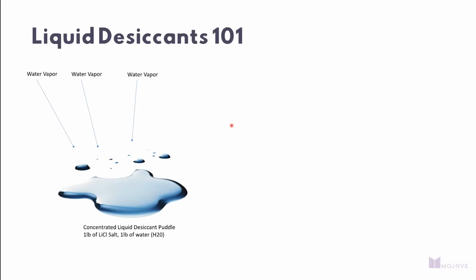A little bit more on liquid desiccants. To conceptualize a liquid desiccant for everyone, if I put a puddle of liquid desiccant in front of you on the table or on the desk, wherever you're sitting or listening, liquid desiccant has a very low vapor pressure, as I said before. It is a concentration of salt, an amount of salt and an amount of water mixed together as a solution. And when exposed to higher vapor pressure air, or saying that differently, air with a higher moisture content, nature likes to be in equilibrium. What happens in that process is there's a natural draw, a passive process, where moisture is pulled out of the air into that desiccant puddle that you're looking at here.